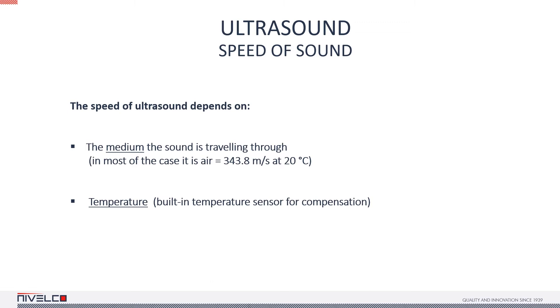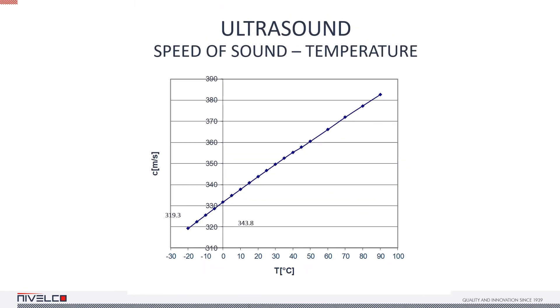Temperature is also an important factor and to compensate for its effects, NIVELCO puts a temperature sensor in all of their ultrasonic devices. This chart shows how much influence temperature has on the speed of sound. This is why temperature compensation is vital to ultrasonic level measurement.